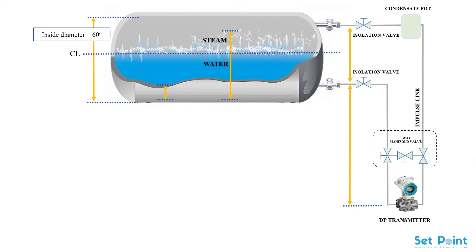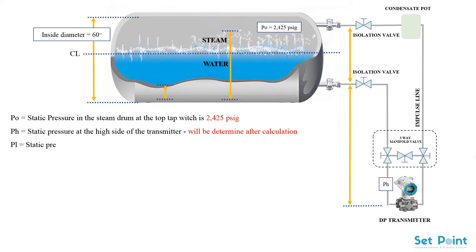Now let's extract the values from the available tables based on the working pressure. PO equals static pressure in the steam drum at the top tap which is 2,425 pounds per square inch gauge. Ph equals static pressure at the high side of the transmitter. Pl equals static pressure at the low side of the transmitter. DS equals density of saturated steam at operating conditions which is 7.24 pounds per cubic foot.